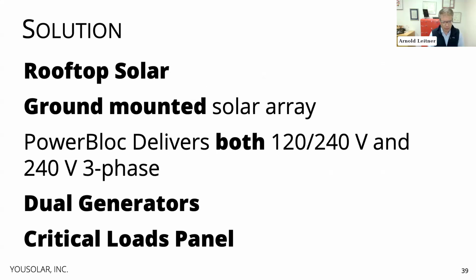We have asked the owner for dual generators, so we have 2 generators that can either by themselves or together add energy to the PowerBloc when we're not having enough sunshine. We also made sure we had a critical loads panel where the generator can also meet the critical load directly. This required making the generator much bigger than we typically do. But now we have redundancy there in case the PowerBloc needs to be serviced, otherwise we don't have any power at that moment.